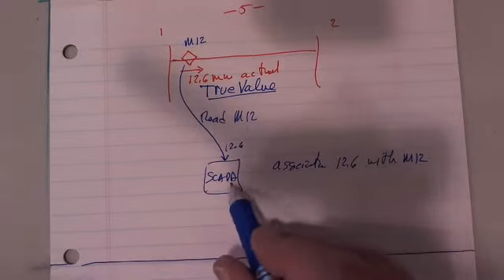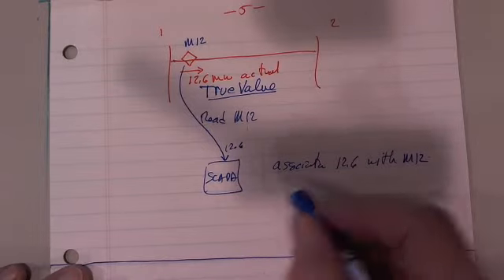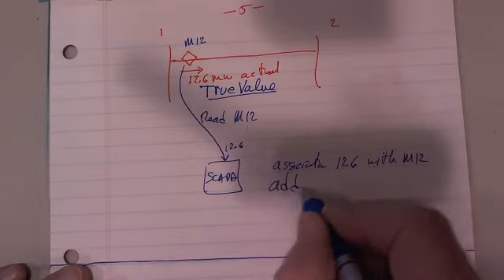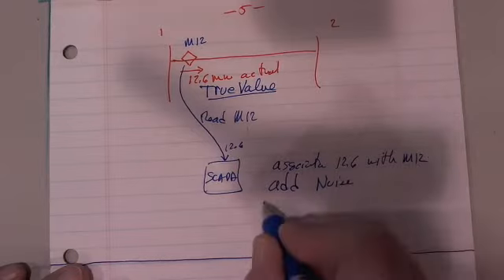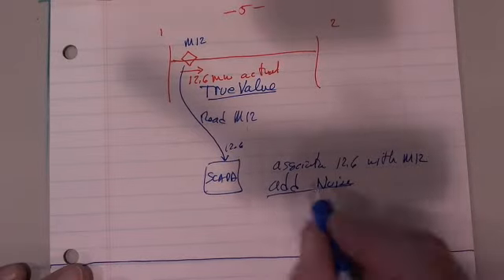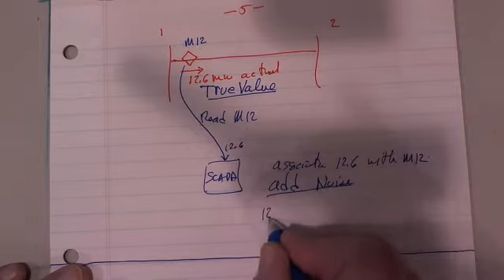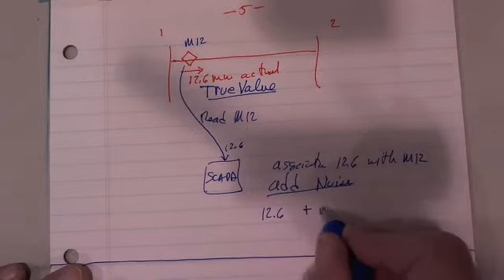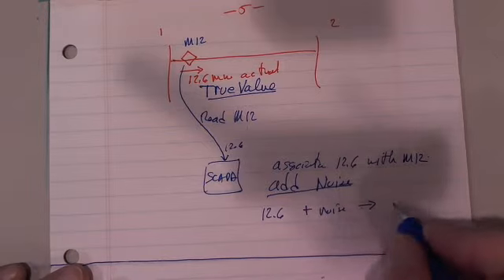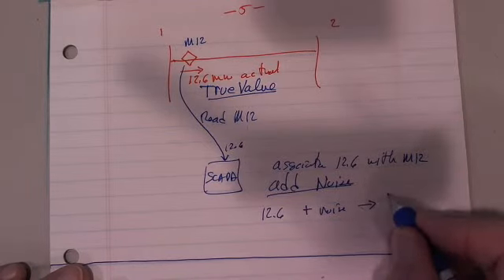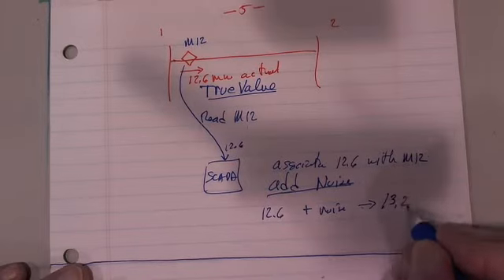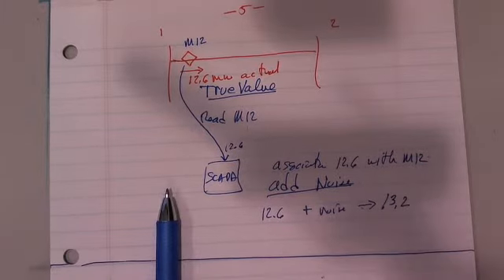So one of the things I can then do inside the SCADA system is add noise. I have a little random number generator that looks at the sigma, and it might take 12.6 and add noise so that whenever the SCADA gets done, it says, oh, that measurement is 13.2. There's an error - I added an error of 0.6 onto there.